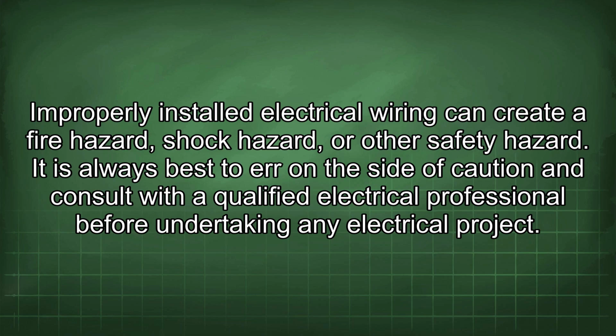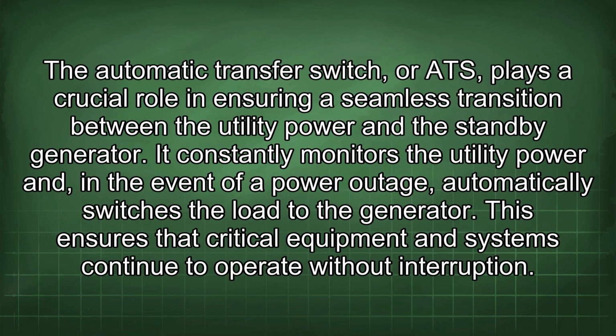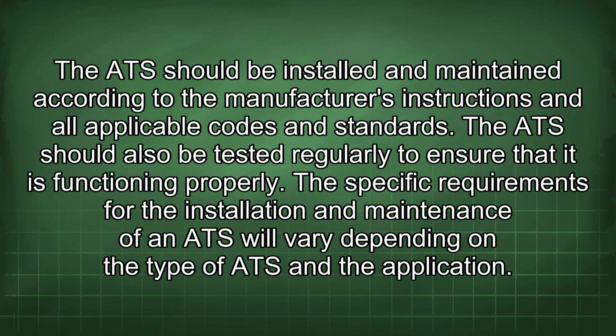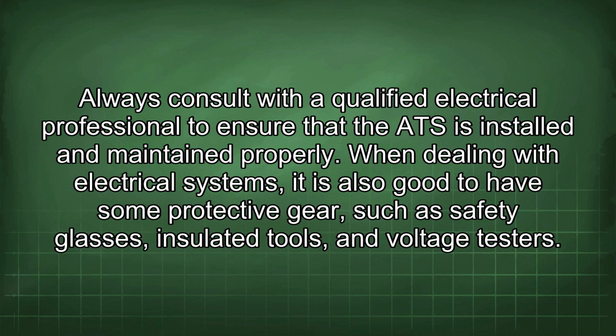The automatic transfer switch, or ATS, plays a crucial role in ensuring a seamless transition between the utility power and the standby generator. It constantly monitors the utility power and, in the event of a power outage, automatically switches the load to the generator. This ensures that critical equipment and systems continue to operate without interruption. The ATS should be installed and maintained according to the manufacturer's instructions and all applicable codes and standards. The ATS should also be tested regularly to ensure that it is functioning properly. The specific requirements for the installation and maintenance of an ATS will vary depending on the type of ATS and the application. Always consult with a qualified electrical professional to ensure that the ATS is installed and maintained properly.